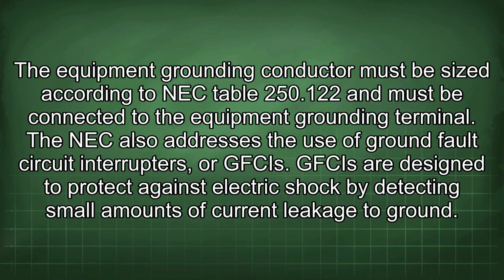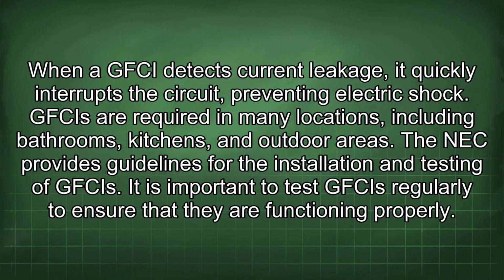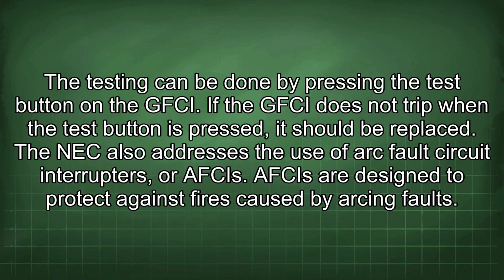The NEC also addresses the use of ground fault circuit interrupters, or GFCIs. GFCIs are designed to protect against electric shock by detecting small amounts of current leakage to ground. When a GFCI detects current leakage, it quickly interrupts the circuit, preventing electric shock. GFCIs are required in many locations, including bathrooms, kitchens, and outdoor areas. The NEC provides guidelines for the installation and testing of GFCIs. It is important to test GFCIs regularly to ensure that they are functioning properly. The testing can be done by pressing the test button on the GFCI. If the GFCI does not trip when the test button is pressed, it should be replaced.